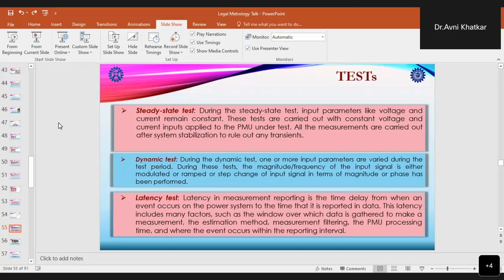So basically, depending upon the different type of dynamic test, the magnitude or frequency of the input signal is changed. In the latency test, the time delay from when an event occurs on the power system to the time it is reported in the data is being tested. This latency includes many factors such as the window over which the data is gathered to make a measurement, the estimation method, the measurement filtering, the PMU processing time, and when the event occurs within the reporting interval. So these three different types of tests are being carried out for the PMUs.